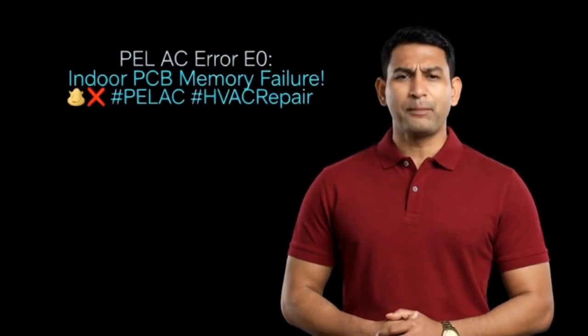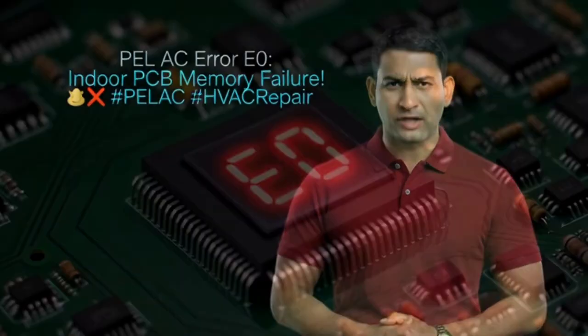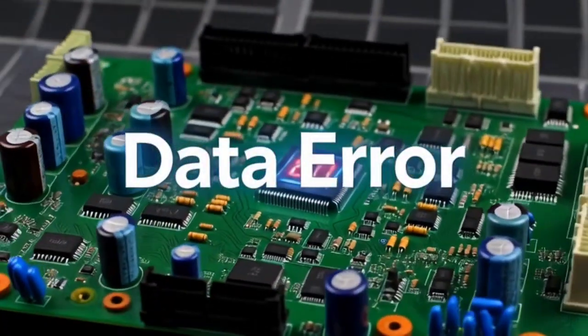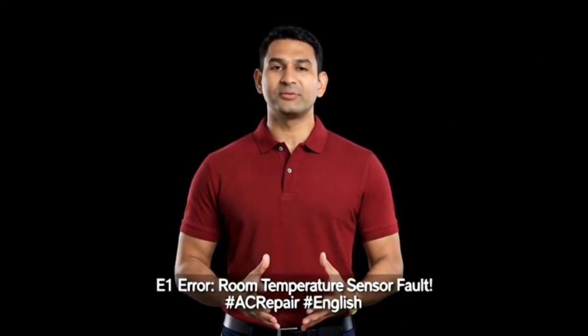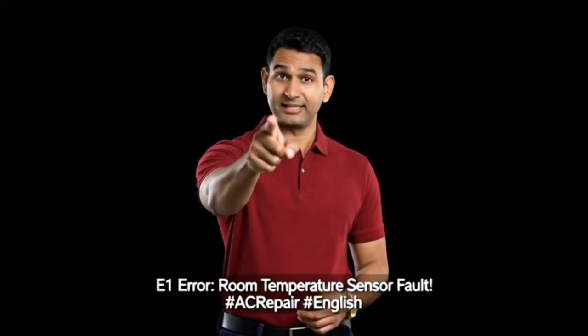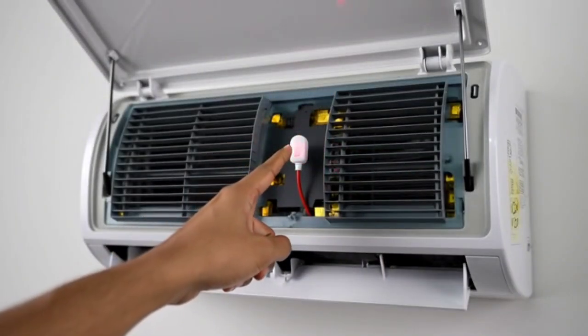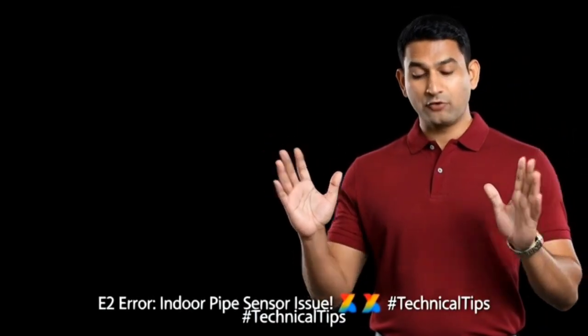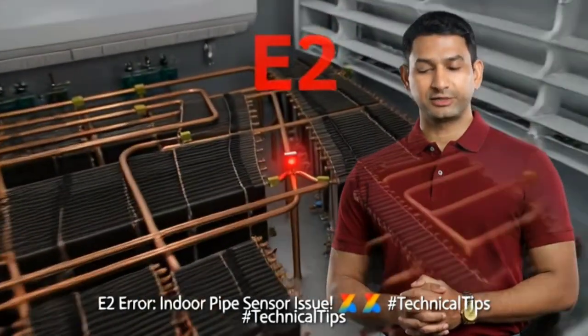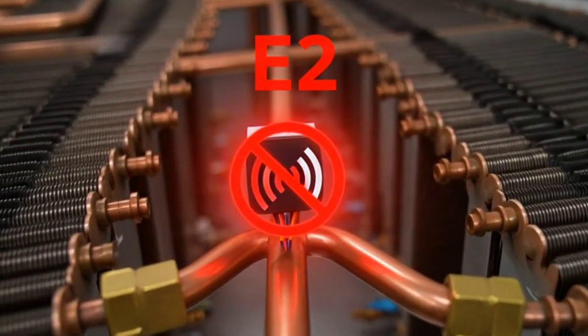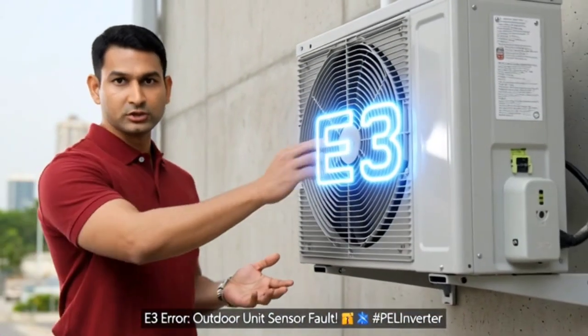E0 error, your indoor PCB memory chip is faulty or corrupted. E1 means your room temperature sensor is disconnected or faulty. E2 indicates a fault in the indoor copper piping temperature sensor. If you see E3, check the sensor on your outdoor unit's coil.